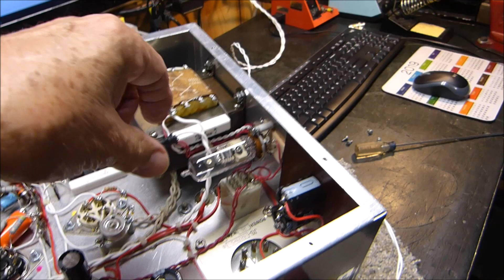To delay the DC from coming up, I've got a delay relay here, a little 115 volt delay relay. You put 115 volts on the filament, and after whatever its timeout is - this one happens to be a 45, the larger ones, this one would be known as a 115 NO45. That means it's got a 115 volt coil. NO means it's normally open, and the 45 says it takes 45 seconds to close. When the time expires and the contacts in this little thermal relay close, it pulls in that relay, and then this relay has got a set of contacts that latches it on. So it's a little latching relay circuit controlled by this thermal relay.